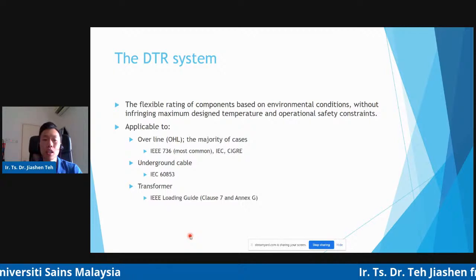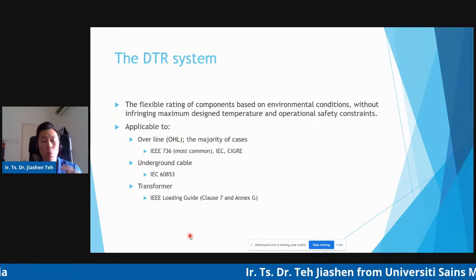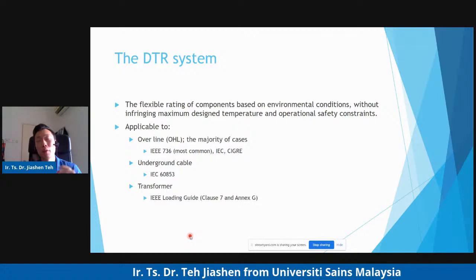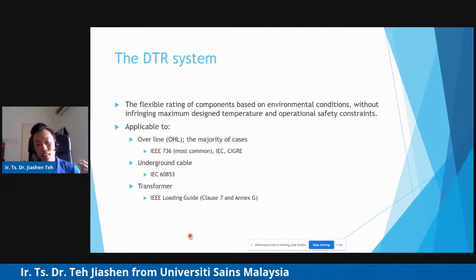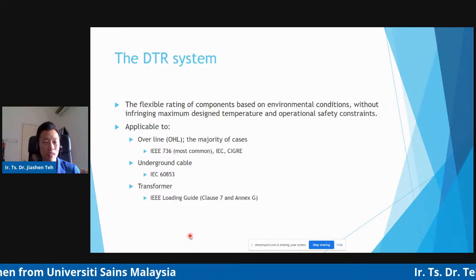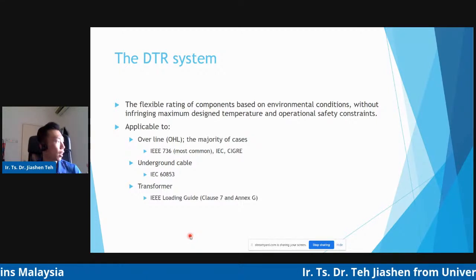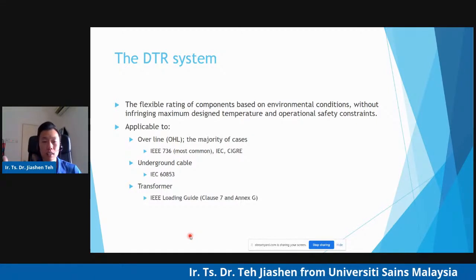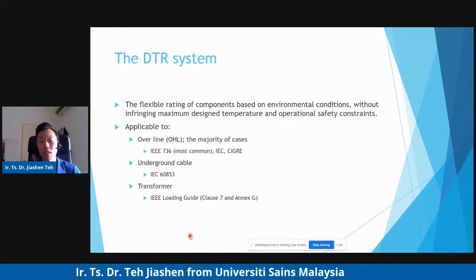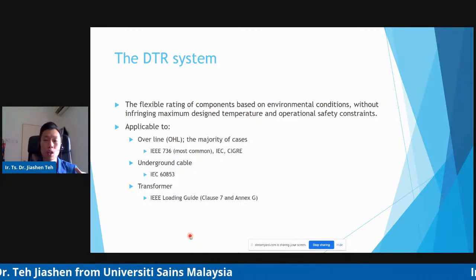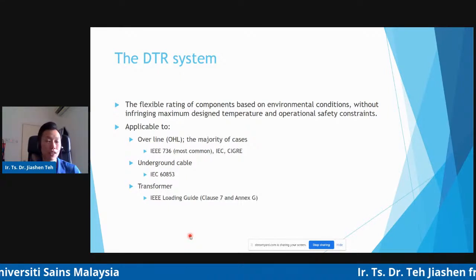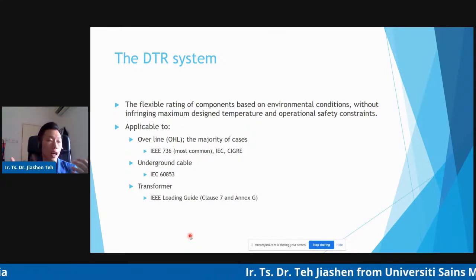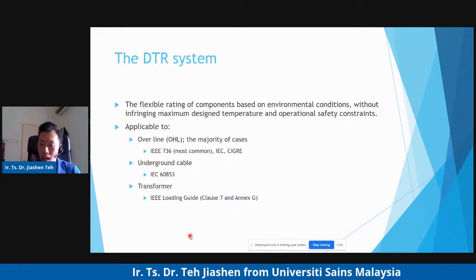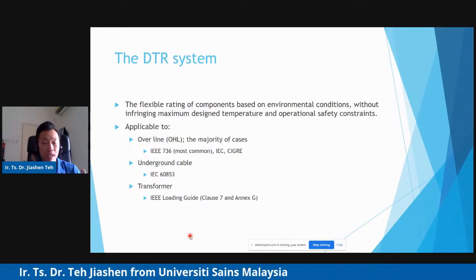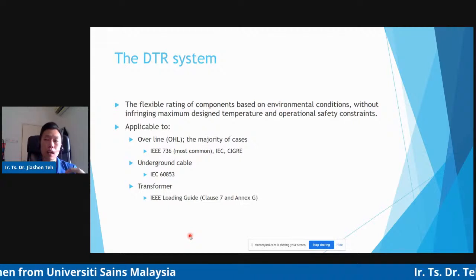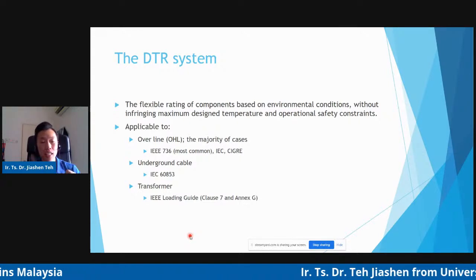Why overhead? Because when we talk about overhead transmission lines, the line is in the open, literally above our head, overhead. It's what we see connecting on transmission towers. Those lines are subjected to environmental conditions: rain, solar radiation, wind speed, wind angle, ambient air temperature. These weather factors will influence the temperature of the conductor.